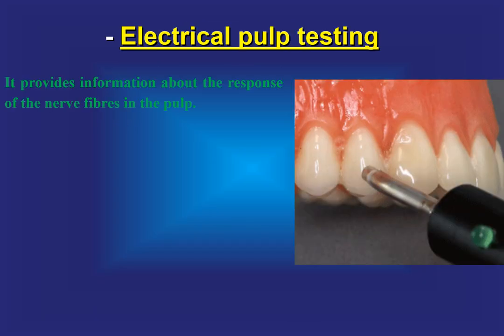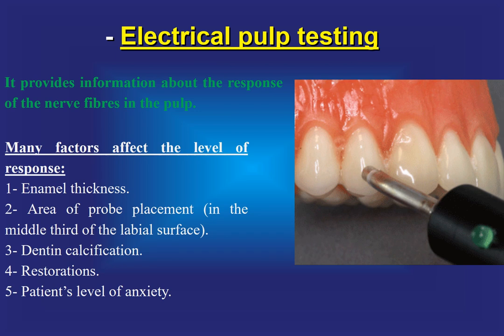Electric pulp tester is a device that provides electrical current. We place it on the labial side of the tooth to transmit electrical current and observe the response of the tooth. It provides information about the response of the nerve fibres in the pulp. Many factors affect the level of response — for example, enamel thickness: the thicker the enamel, the more insulation.